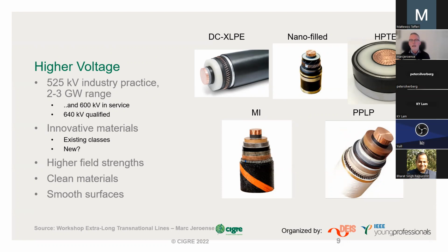Recently, I saw a new announcement of a cable manufacturer that has qualified their system for subsea use, using a somewhat higher operating temperature and stating that they can reach 2.5 gigawatts. We also know there is at least one cable system in service at 600 kV, using PPLP technology. I also know one manufacturer having fully qualified, by PQ test and type test, at the 640 kV level. So 525 is the sweet spot, but there are some signs of already increasing voltages.